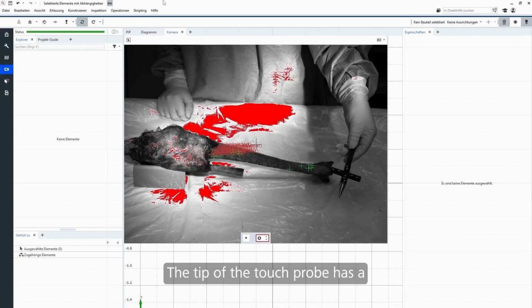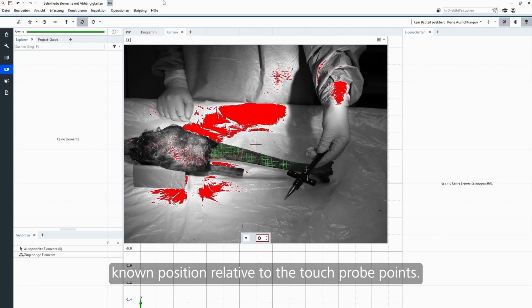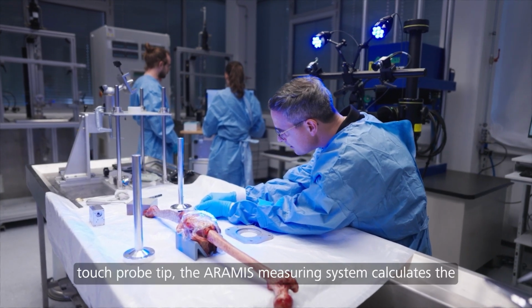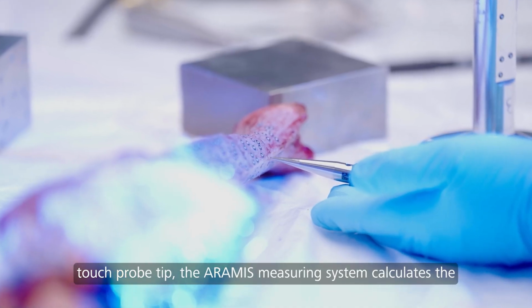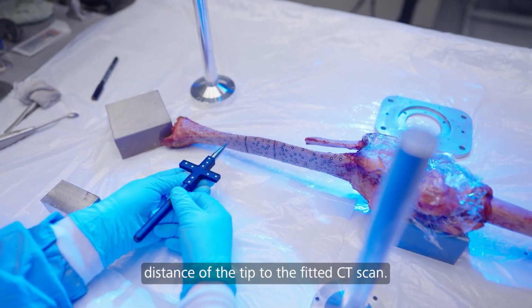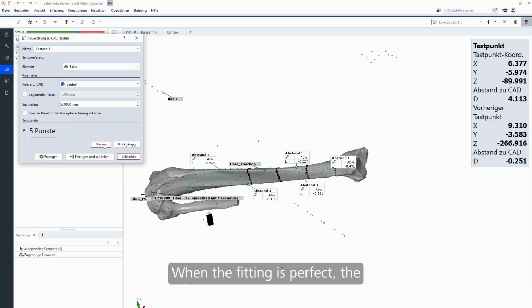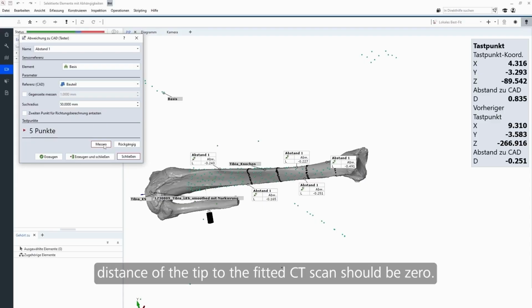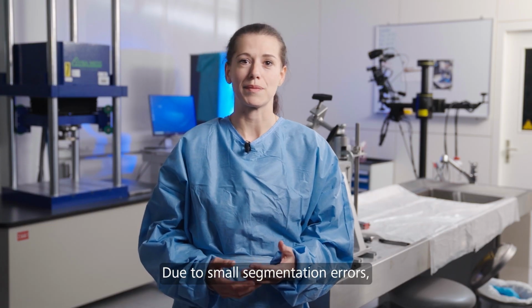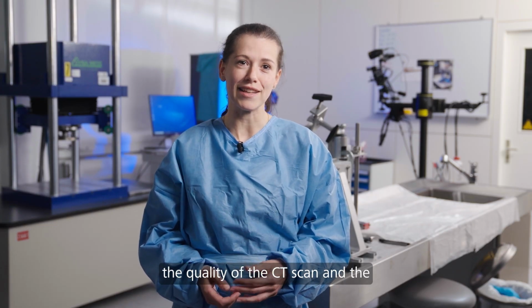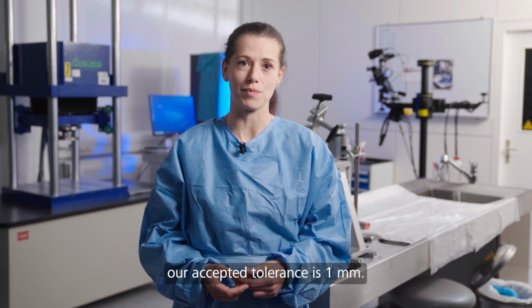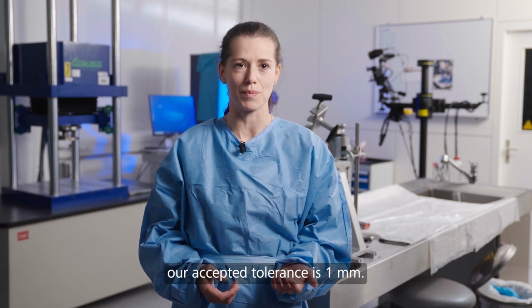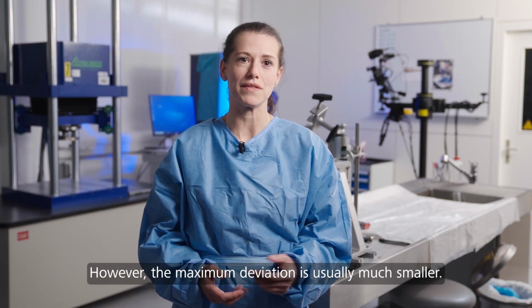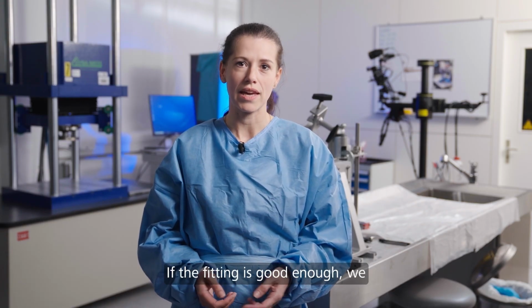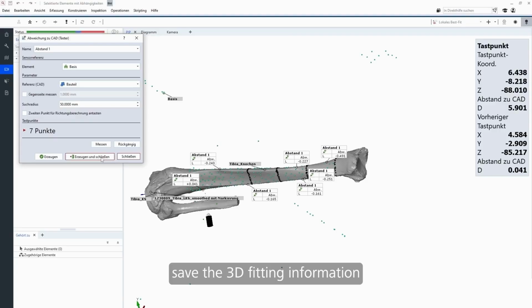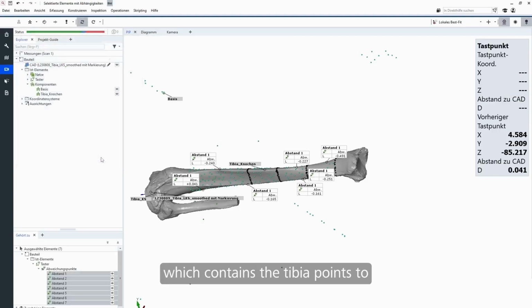The tip of the touch probe has a known position relative to the touch probe points. When palpating the bone using the touch probe tip, the Aramis measuring system calculates the distance of the tip to the fitted CT scan. When the fitting is perfect, the distance of the tip to the fitted CT scan should be 0. Due to small segmentation errors, the quality of the CT scan, and the possibility of scraping off some bone during preparation, our accepted tolerance is 1 mm. However, the maximum deviation is usually much smaller. If the fitting is then good enough, we save the 3D fitting information, which contains the tibia points to CT scan information.